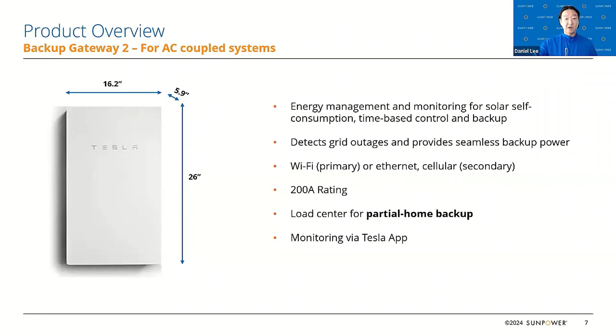So that's the system. Again, we can install up to 4 units. That is the maximum. Tesla says it meets UL 9540A performance criteria. What that means is that the units can be installed as close as 6 inches from one another. It all depends on the AHJ. I will say that with Tesla's training, they say that with UL 9540A you can install as close as 3 inches. But from the information that we have, UL 9540A generally allows you to install as close as 6 inches. But again, it all depends on the AHJ.